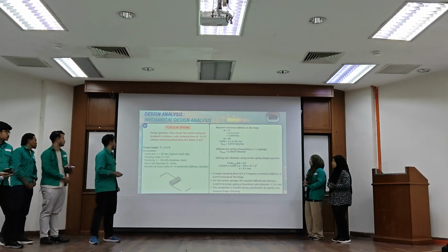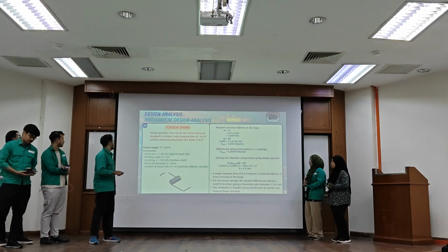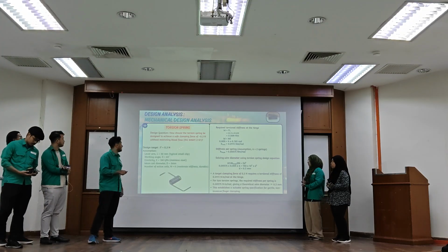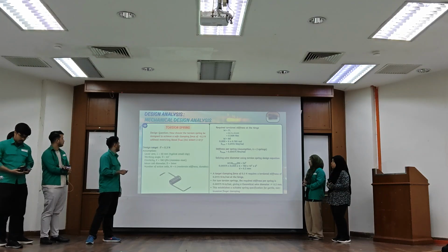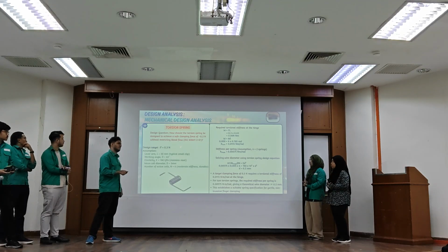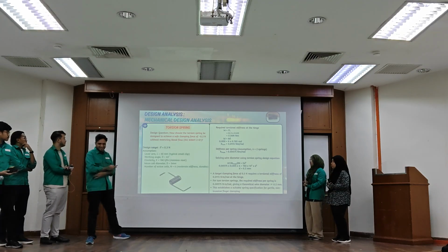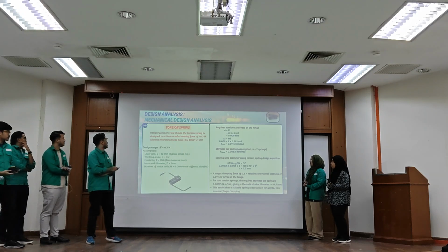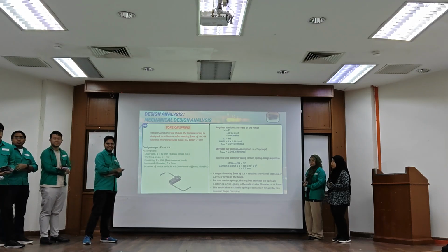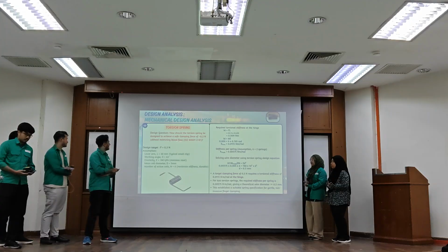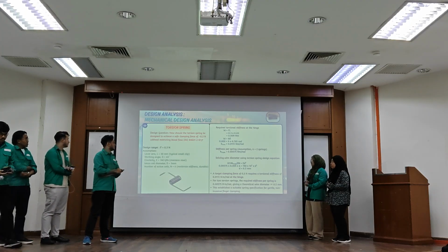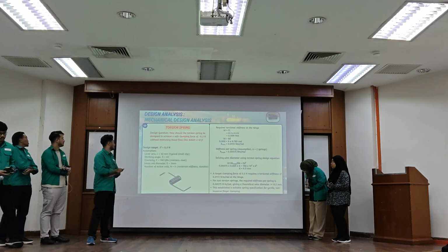Moving on to the design analysis, which is mechanical. The international medical standard requires 0.3 Newton force for the clamping.